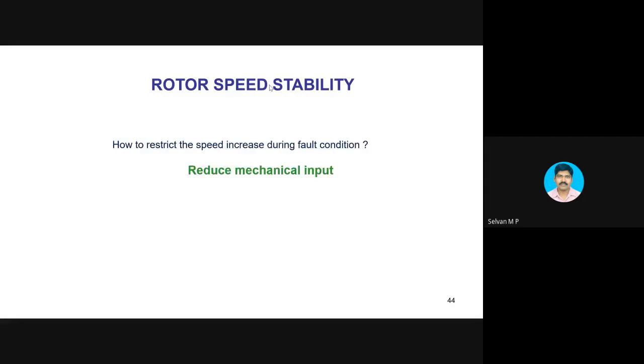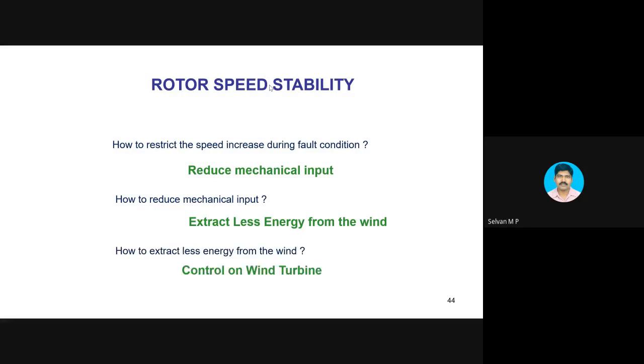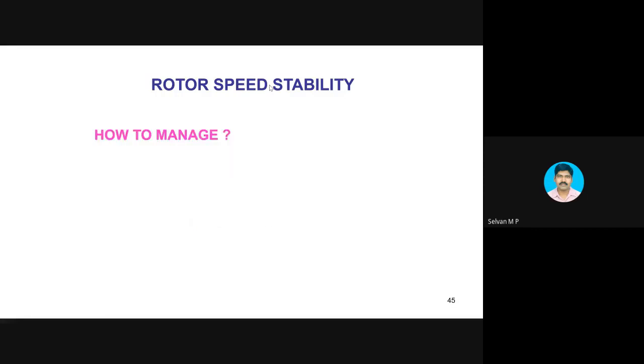So how do I achieve that? I should reduce the mechanical input during the fault period. It is not possible. It is not a hydro turbine. It is not a thermal steam turbine. I cannot control the input. It's a wind turbine. It's very difficult. Then how to reduce mechanical input if I would like to? Then I have to extract very little energy from the wind. How to extract less energy from the wind? I have to do a control on the wind turbine. Yes, of course, there is a method called pitch control, which can control the mechanical energy extracted from the wind, but the fault duration is very short. Within that time, activating the pitch control is tedious. It cannot be done. So we have to deal with only the electromagnetic torque.